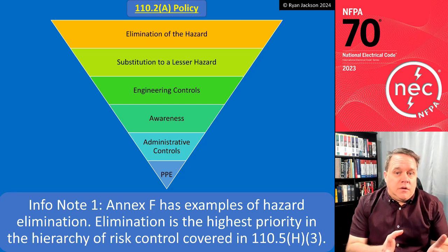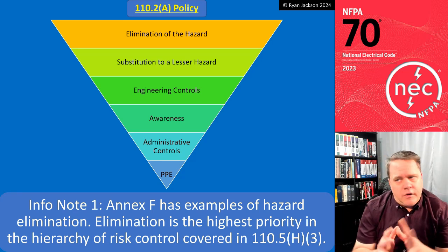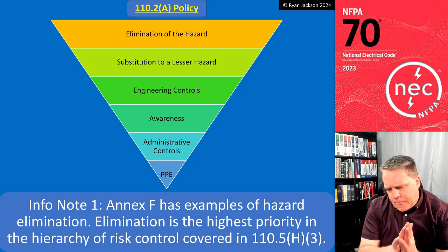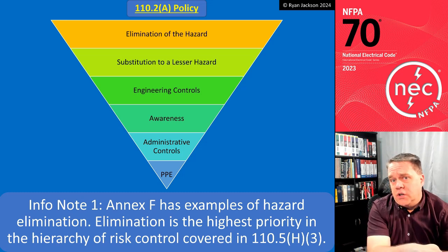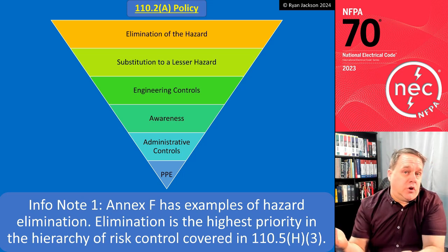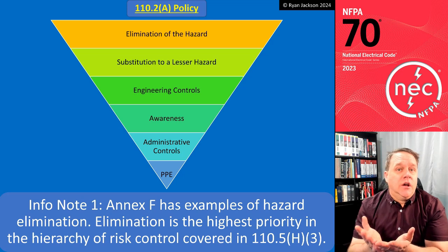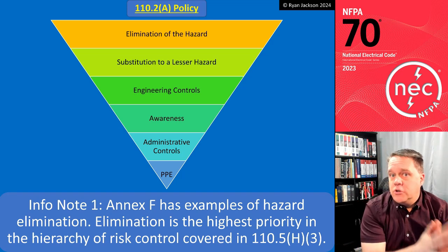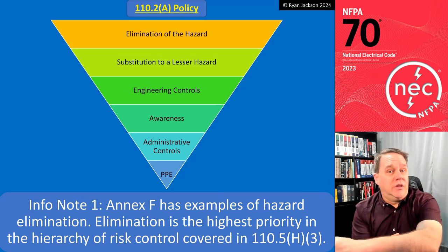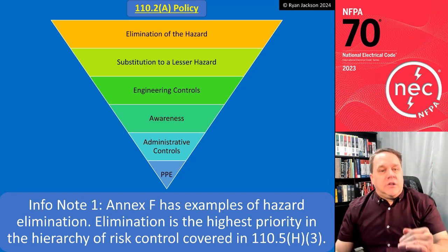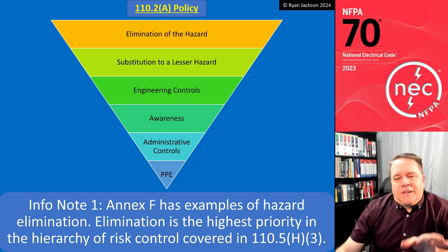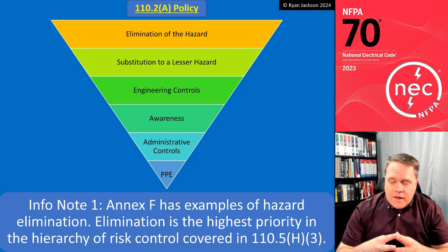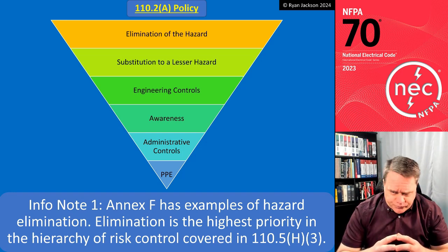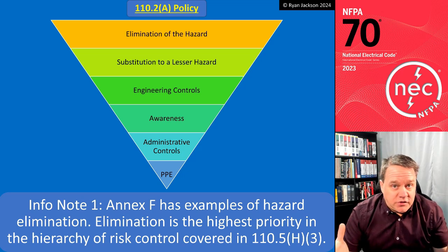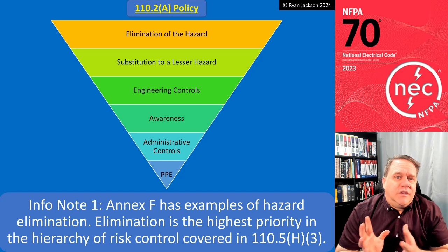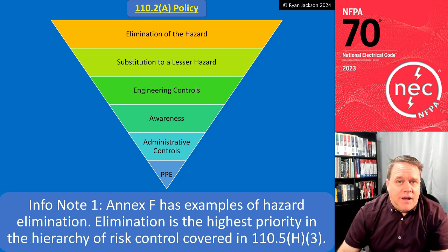But if you can't eliminate the problem? Well, substitute to a lesser hazard. Maybe I'm troubleshooting a motor circuit. Can I troubleshoot the low voltage control circuit instead of the power circuit? Might be a good example of substituting to a lesser hazard. Is there a hazard in troubleshooting the control circuit? Sure. Is it the same hazard as troubleshooting the line voltage to the motor? No, it's not. Engineering controls, awareness, administrative controls, and then the last one is wearing PPE. Wearing PPE is the least effective way of removing risk, right, and removing hazard. So PPE is always the last resort. The first thing we want to do is to eliminate the hazard.